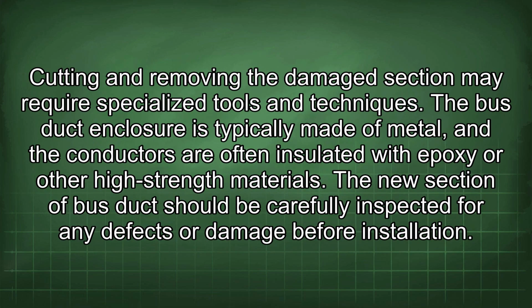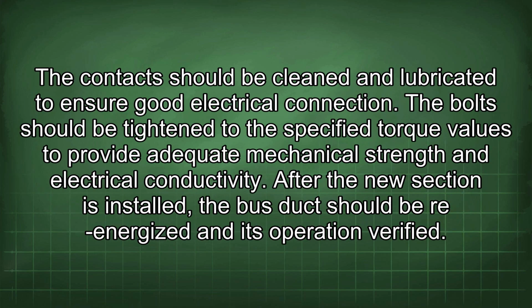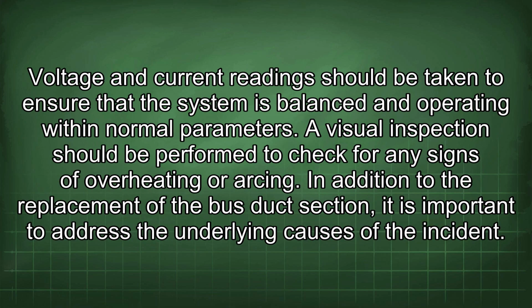Cutting and removing the damaged section may require specialized tools and techniques. The bus duct enclosure is typically made of metal, and the conductors are often insulated with epoxy or other high-strength materials. The new section of bus duct should be carefully inspected for any defects or damage before installation. The contacts should be cleaned and lubricated to ensure good electrical connection. The bolt should be tightened to the specified torque values to provide adequate mechanical strength and electrical conductivity. After the new section is installed, the bus duct should be re-energized and its operation verified. Voltage and current readings should be taken to ensure that the system is balanced and operating within normal parameters. A visual inspection should be performed to check for any signs of overheating or arcing.